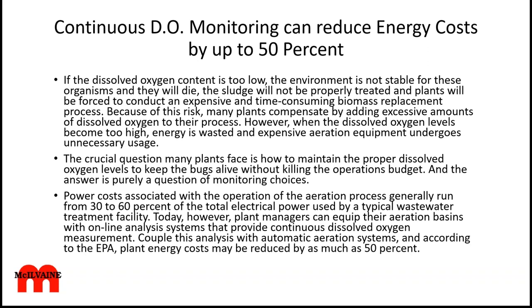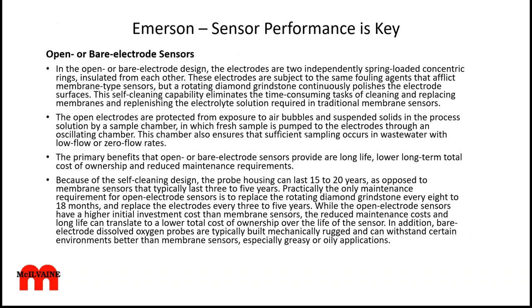Dissolved oxygen monitoring is critical to minimizing the amount of energy you use, because aeration equipment is a good portion of the total energy consumed, 30 to 60% in fact, of a typical wastewater facility. So just getting the right amount of oxygen in there is important.